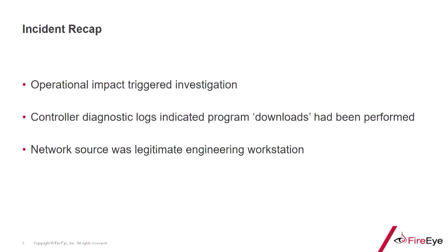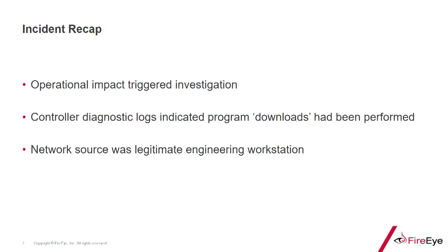The local triage team responding to this — engineers and operators from the asset owner — reviewed controller diagnostic logs and noticed that in the period leading up to the outage, some downloads of code and application logic to a controller had been performed. They noticed that the source of those downloads was from a legitimate engineering workstation, but they knew from reviewing their change management documentation that no legitimate changes were intended during that time period.